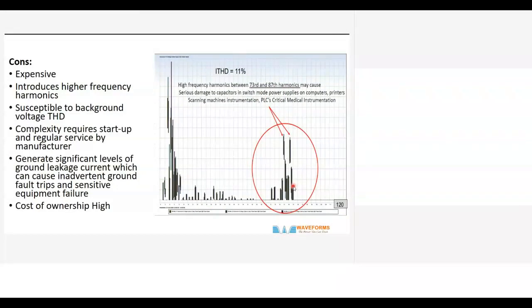They introduce higher frequency harmonics. So you may have EMI issues also with this, because the power analyzer measures up to the 50th harmonic only. Above that, they don't measure. You have to use a spectrum analyzer. So it does introduce some high frequency harmonics, which can interact with your electrical network and cause other issues. So they are not totally good power conditioners as such.